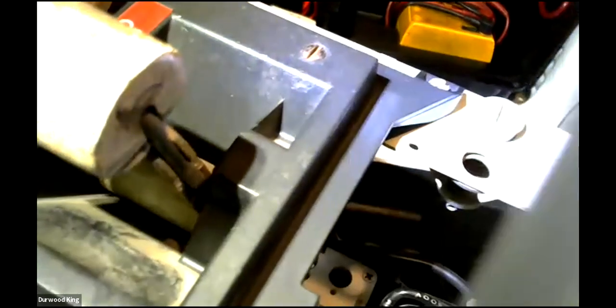let's see. Those are heater part numbers right there. They're X numbers, so I don't know what brand that is, but whatever brand it is, you'll have a chart. If it's Allen Bradley or Schneider or whoever it is, there'll be a dedicated part number for so many amps. You see that? Mm-hmm. It says heater type number. So there, where everything is X something, this one is a FH. But see, this is Cutler Hammer. Cutler Hammer had their own numbers. And that's actually Westinghouse. If you see down in there, it's actually a Westinghouse. So all these part numbers on the heaters and all, they're going to be Westinghouse numbers. So anyway, getting back to this.